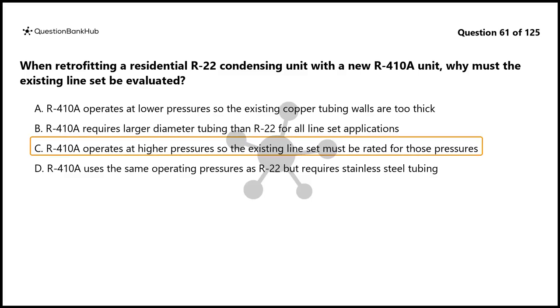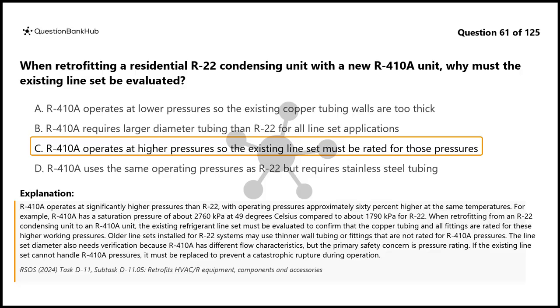The correct answer is C. R410A operates at significantly higher pressures than R22, with operating pressures approximately 60% higher at the same temperatures. For example, R410A has a saturation pressure of about 2,760 kilopascals at 49 degrees Celsius compared to about 1,790 kilopascals for R22. When retrofitting from an R22 condensing unit to an R410A unit, the existing refrigerant line set must be evaluated to confirm that the copper tubing and all fittings are rated for these higher working pressures.